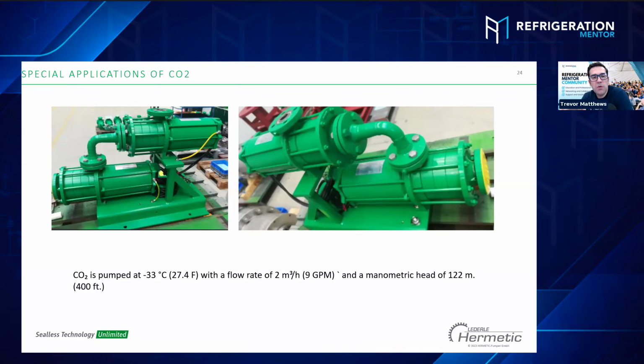I have a question about this picture, because I know we've talked about it before. We don't want any short radius, we don't want to be curving right away because we could cause issues going into the circuit. When you have it set up like this, are there no issues with pumping directly into the next pump with that 90 there, with only about 4 or 6 inches away from each pump, or do you have to have a longer distance, like 4 feet, so you don't have any cavitation or turbulence, things like that?